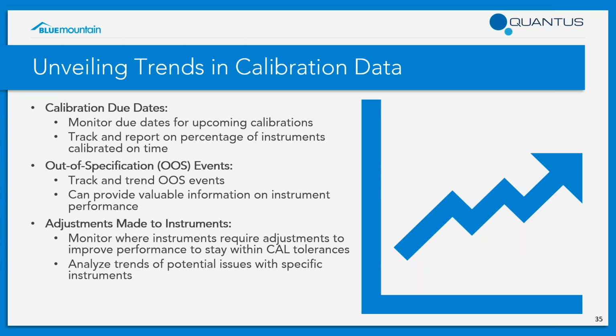And then in the previous slide, Dave talked about adjustments. Some customers will choose to monitor how often they're adjusting a device. Maybe it wasn't outside of calibration, but every time you're servicing it, there's an adjustment to be performed. You may want to do a deeper look into that. Maybe the instrument's starting to drift more often than it should and may need replacement.